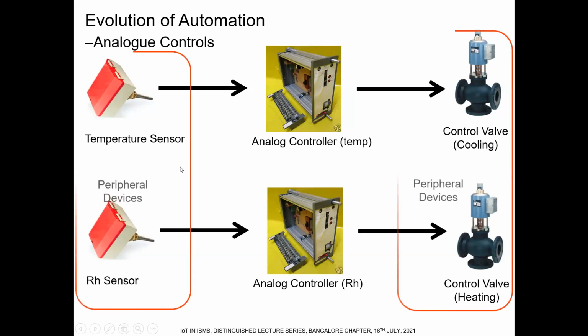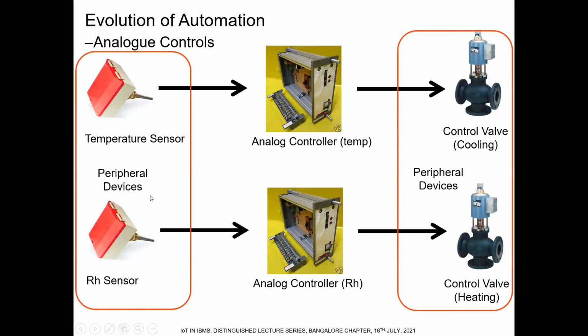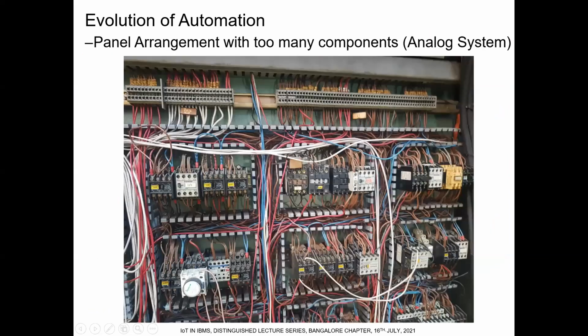Okay. These devices, we used to call them peripheral devices because they are located in the field. These were located on the panel, inside the panel. These were field devices, input devices, output devices. You can see here peripheral devices, sensors, actuated devices, output devices. A panel those days was such a complicated device because there were too many relays, too many controllers, too many complications, timers, this, that, and the other. The panel was such a complicated component of the automation process.